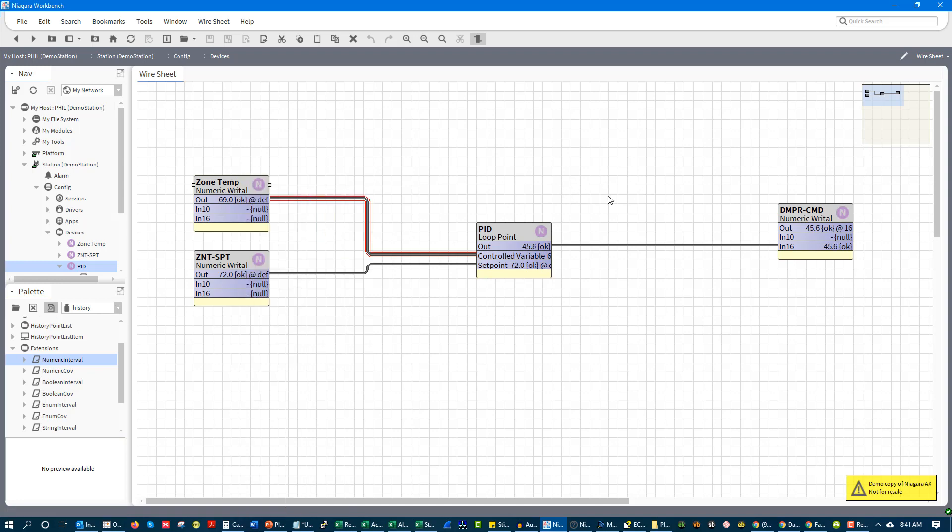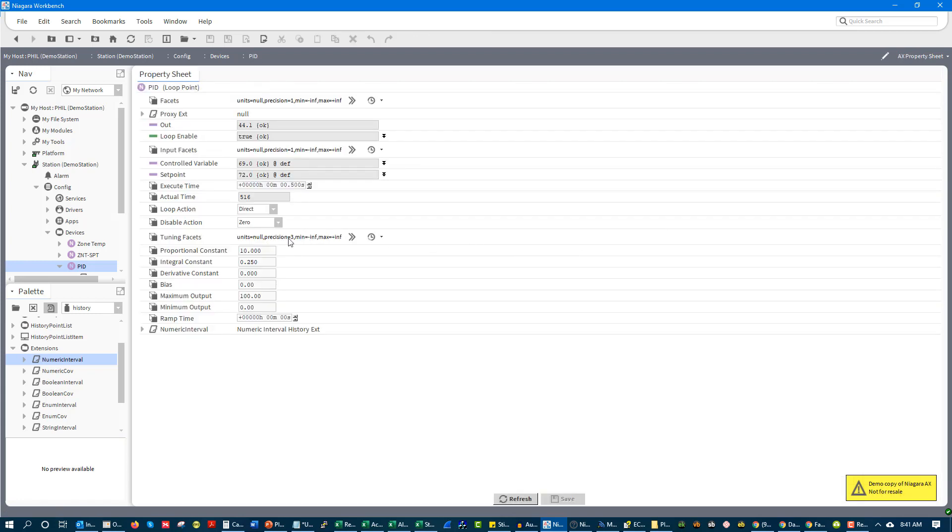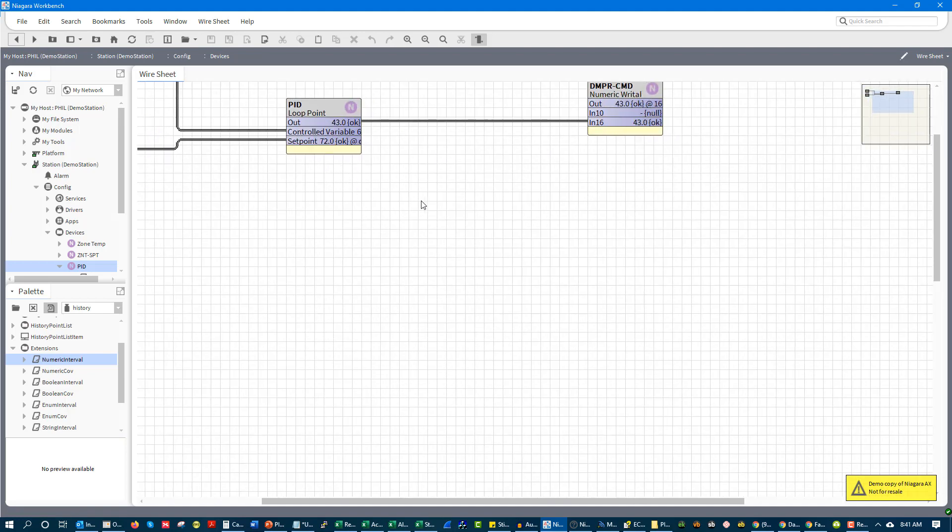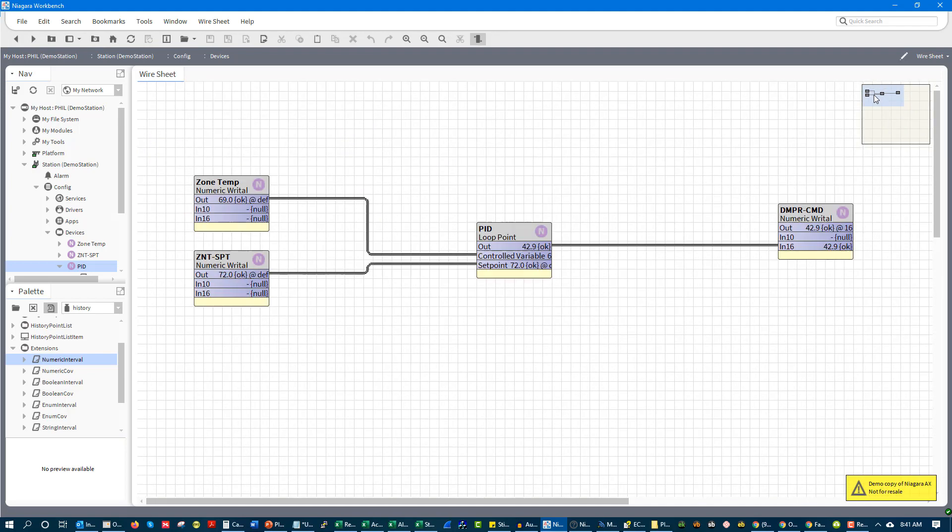And so what's happening is our proportional stays the same because it's proportional band times error. But our integral times error is going to accumulate each time the loop cycles. And we can see that the loop cycles every half a second. And so if we wanted to make that faster, we could do so by going and actually changing our loop cycle time.